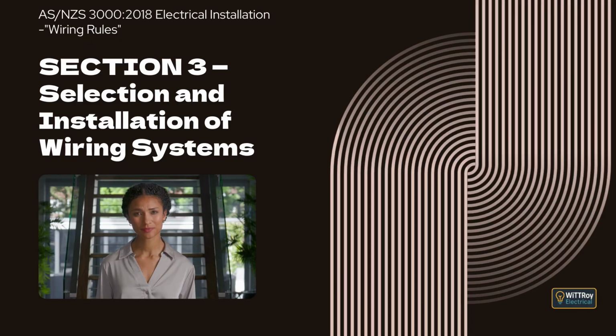Clause 3.9.4.3 Wiring systems under wall lining or roofing material. This clause states that wiring must not be installed in the narrow spaces formed between wall or roof linings and their immediate supporting members, as these locations present a high risk of damage. Clause 3.9.4.3.2 Protection required. This clause explains that where wiring passes through structural members or is fixed close to supporting members, appropriate protection must be provided to reduce the risk of mechanical damage.